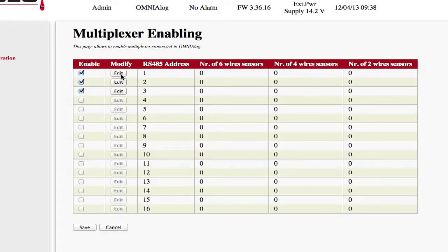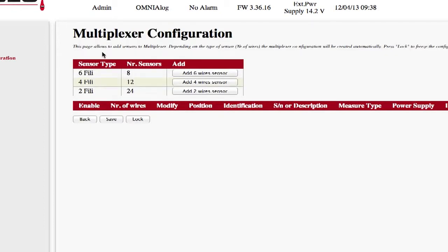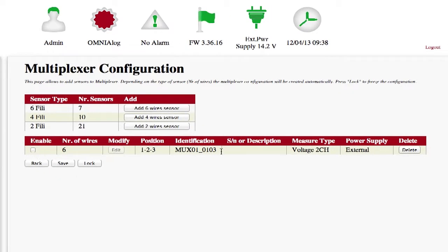Press the Edit button of the multiplexer that you have to configure. A new page will open called Multiplexer Configuration. Via the first panel on this page, you will be able to add the instrument type connected to the multiplexer via three buttons: Add 6 Wire Sensor, Add 4 Wire Sensor and Add 2 Wire Sensor. Clicking, for example, on Add 6 Wire Sensor will add a 6 wire instrument. The other two buttons function in the same manner.